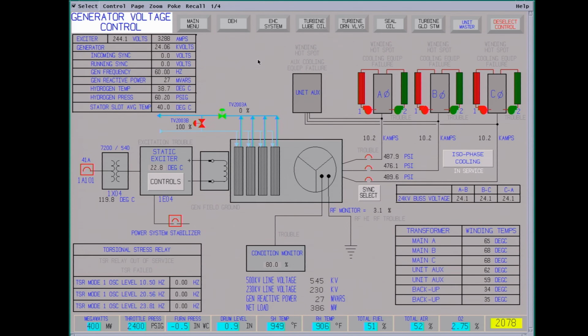This is the generator voltage control screen. These are the step-up transformers. They're full of oil, so you're using transformer oil to cool them. I just have one pump running on this one going to the cooler. Each phase has its own transformer. There's just one pump running.